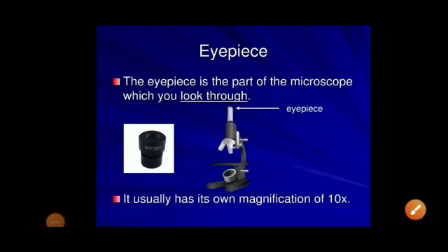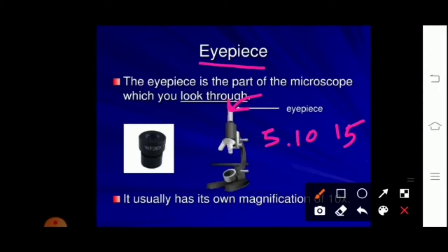Now moving toward the optical parts of the microscope. The first part is the eyepiece. It is called the eyepiece because when you look through it, your eyes come directly into contact with its first lens. It is also called the ocular. It usually has its own magnification of 5x, 10x, or 15x — meaning it magnifies the size of the object up to 5, 10, or 15 times. We can use the eyepiece as per requirement.